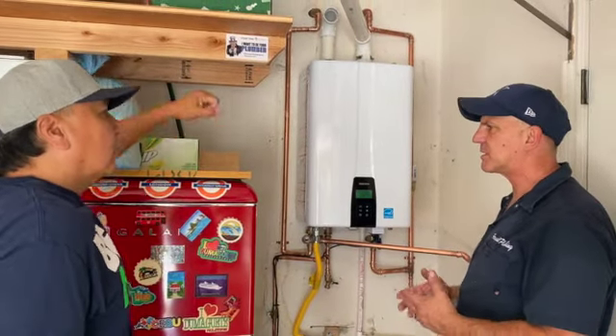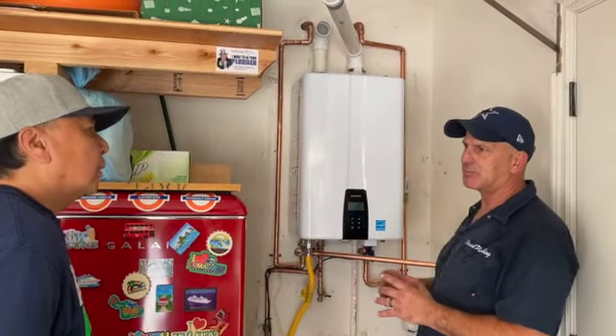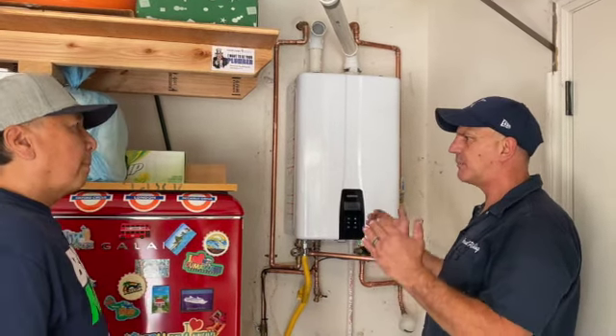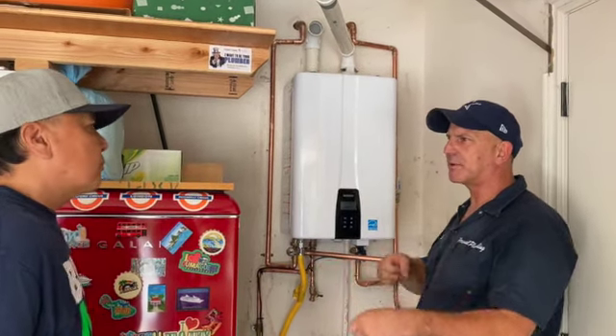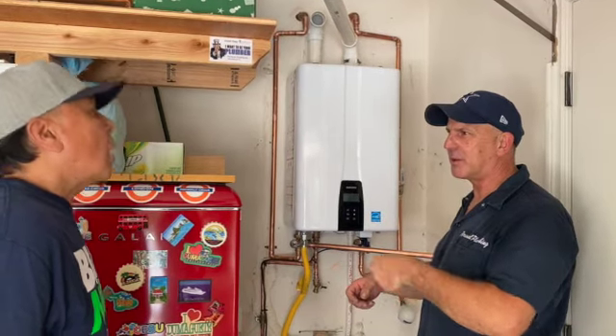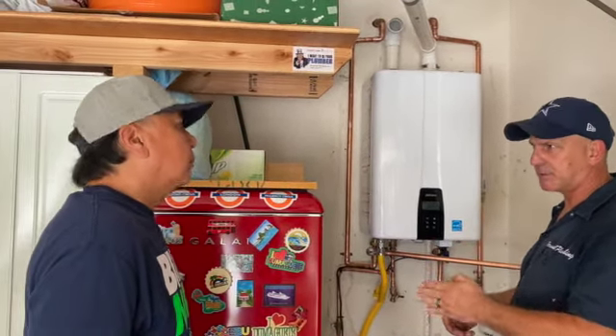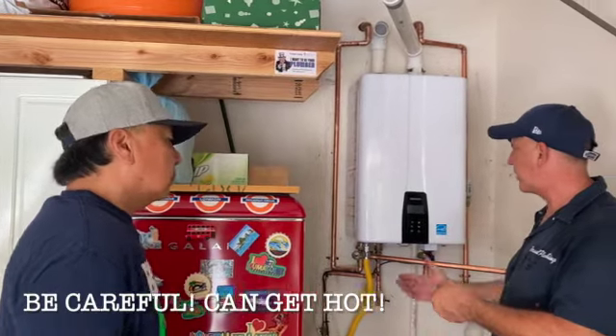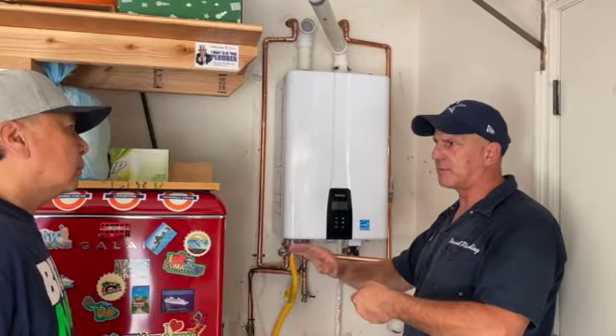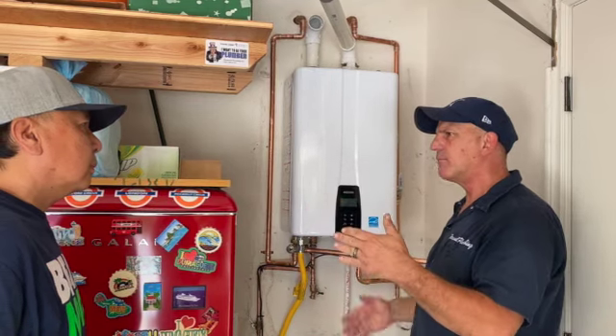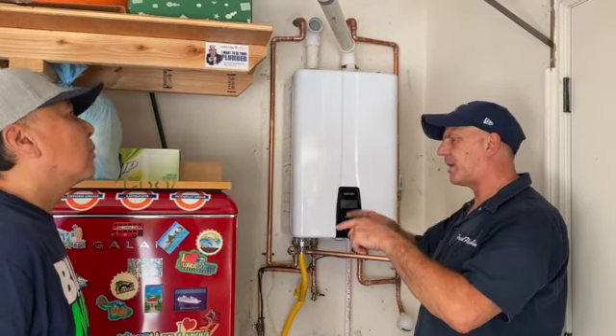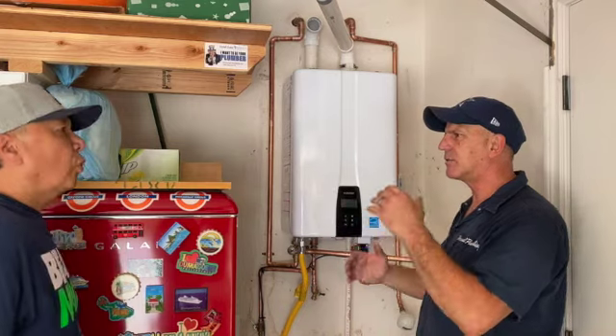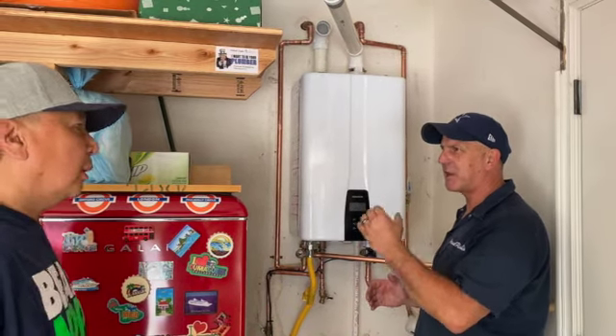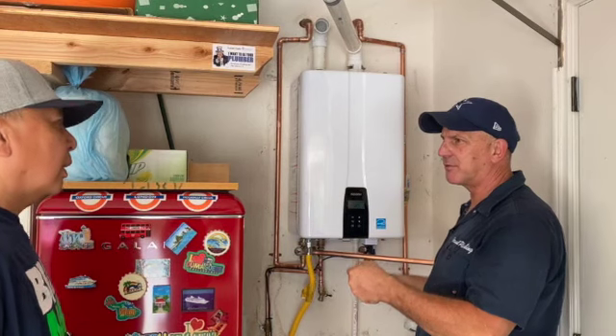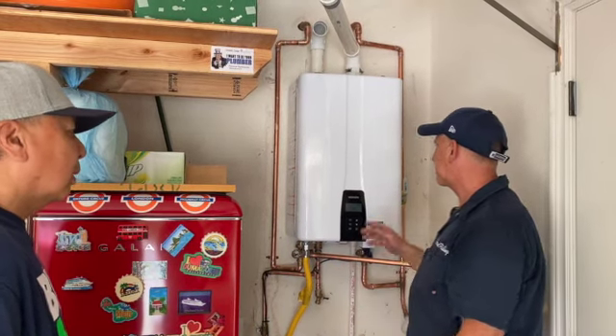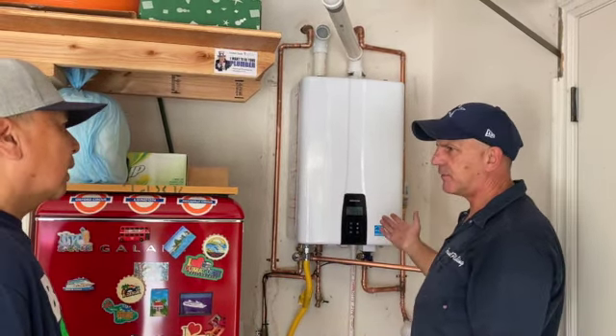So what happens is, inside your showers, because you have that balancing spool in your shower valves, your temperature is going to feel hotter at single handle fixtures since there's no mixing going on there. When you turn that on, you get direct 120 degree water, which cools down a little as it travels to the furthest fixture. But in a shower with the balancing spool, you've got cold and hot water mixing together, so it will never feel as hot at the shower as at your single handle fixture. So if it doesn't feel hot enough in your shower, you'll need to come out here and turn this up a bit.